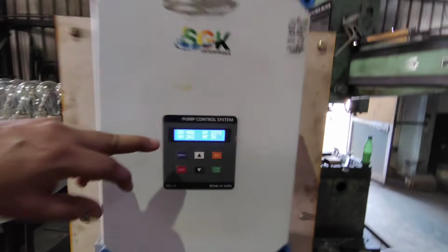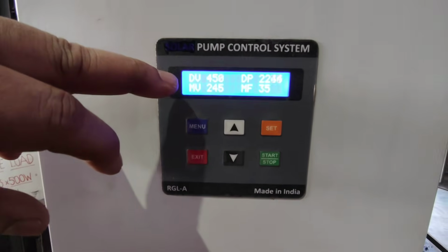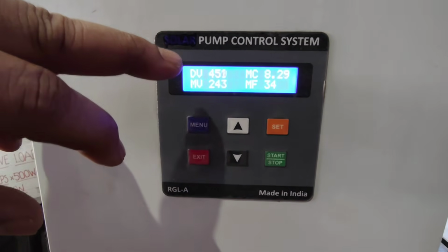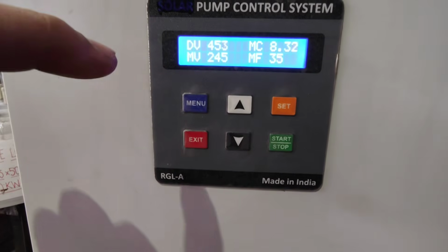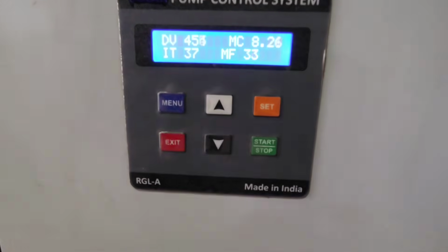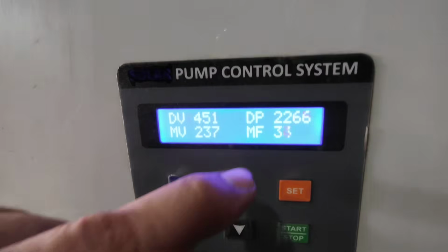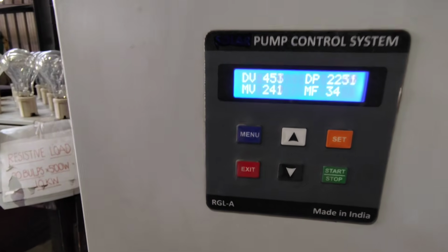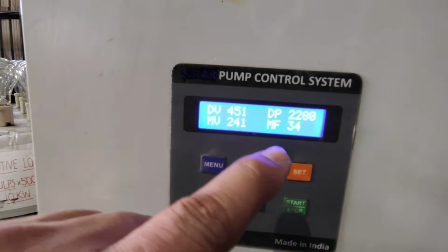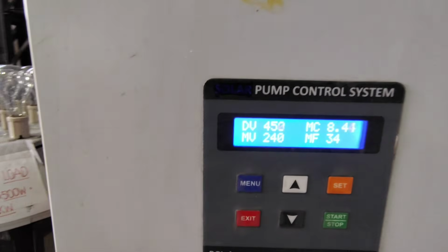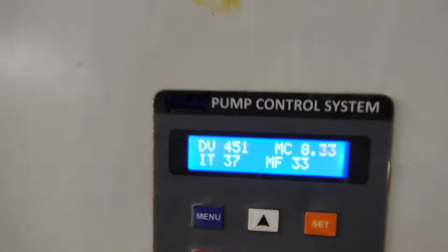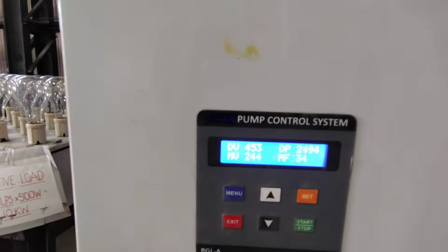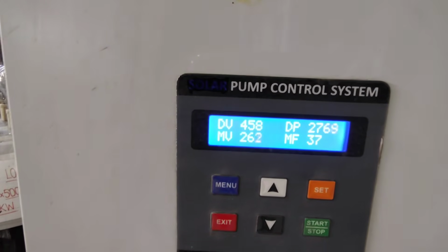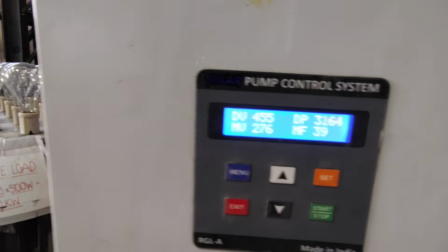So now we will be showing you the pump control system. That is, your DC voltage is 452 DC voltage. So motor voltage is 240. Motor current is 8.5, and here motor frequency is 34. Motor frequency 34. Motor voltage is 242. At 242 we are running the pump. 3-phase 415 volt, 50 hertz, 10 HP, 7.5 kilowatt pump. Monoblock pump.